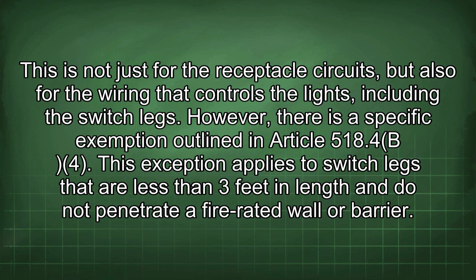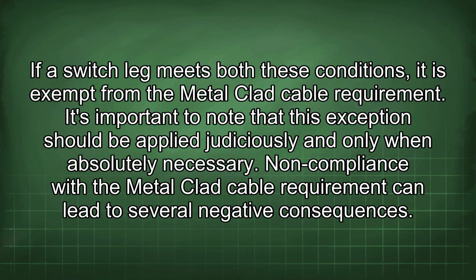legs. However, there is a specific exemption outlined in Article 518.4(B)(4). This exception applies to switch legs that are less than 3 feet in length and do not penetrate a fire-rated wall or barrier. If a switch leg meets both these conditions, it is exempt from the metal-clad cable requirement. It's important to note that this exception should be applied judiciously and only when absolutely necessary.